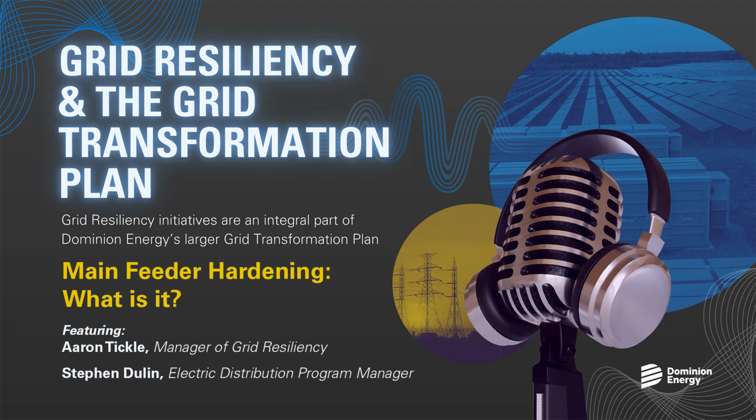A lot of times when we're out meeting with customers or sending some letters out or receive some calls or speak with customers face to face, we get asked, what do some of these new standards consist of? So just real quickly, a few of the new standards would include installing higher class poles, meaning thicker, taller poles, which will be set deeper in the ground, 10-foot fiberglass cross arms, which replaces our old standard of 8-foot wood arms, and additional protective devices and circuit ties will also be installed, which will help us isolate damages during some of these restoration events. Another large component of the program will also be tree trimming. Just going through and trimming trees will also help prevent additional damages during some of these storm events.